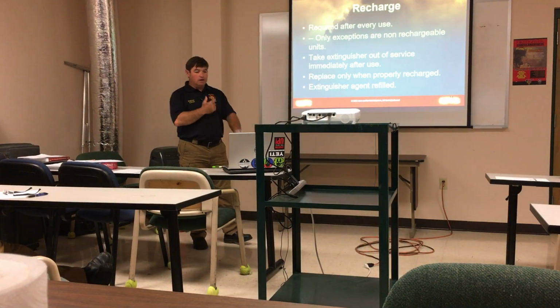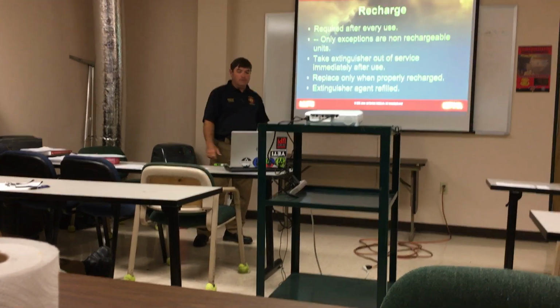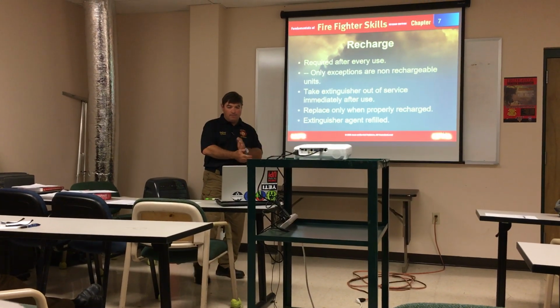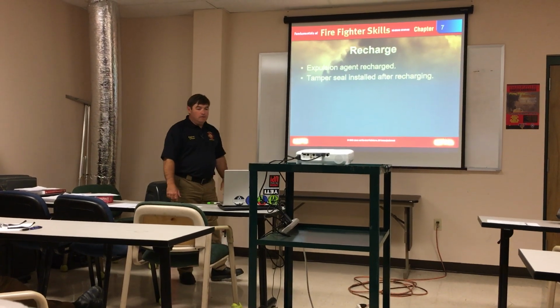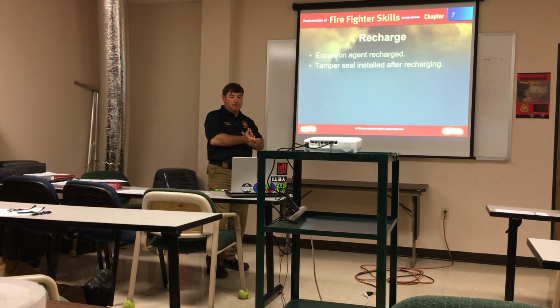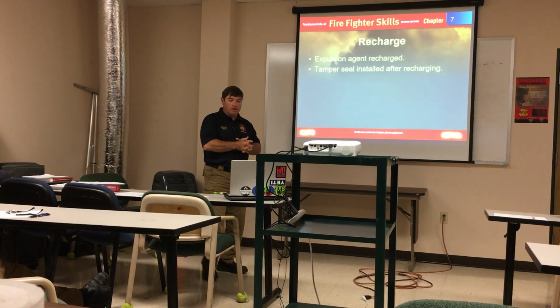Take the extinguisher out of service immediately after use, and replace only when properly recharged. Extinguisher agents have been refilled. Make sure that the expulsion agent, which is the pressure for it, has been recharged, and all the tamper seals installed after recharging.